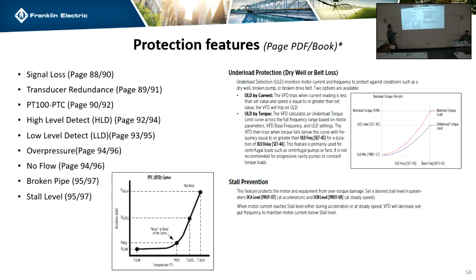Protection features. Okay. Signal loss is what I was talking about at the very beginning. If the drive is set to look at an input for an analog signal and it doesn't see it, you will get a fault that says analog loss, or it'll say ACI lost, AVI lost. It will tell you what input it is and that it can't see it. You can have transducer redundance. You cannot have two transducers and then average the two, but you can have two transducers and have one be a backup, and you can have transducers where one is the primary and the other one's an analog trigger.